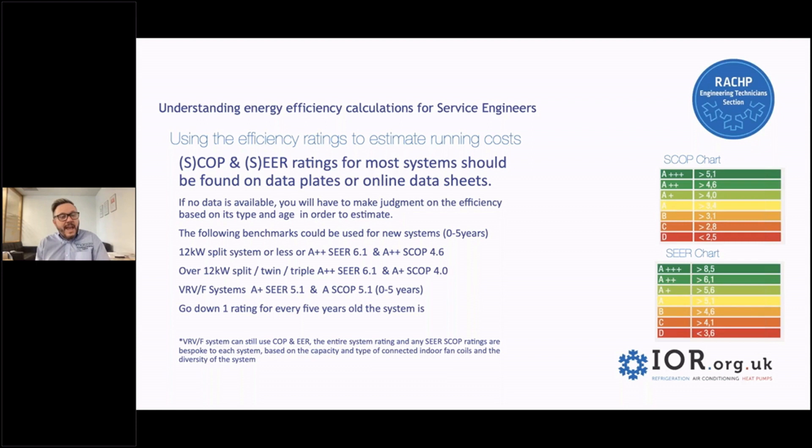If I were looking at a 12 kilowatt system or less and couldn't get any information on it — which again would be super rare — then I would choose A++ as a SEER rating of 6.1, and an A++ SCOP rating of 4.6, because they're all high when you're looking at new systems, especially for smaller than 12 kilowatts.